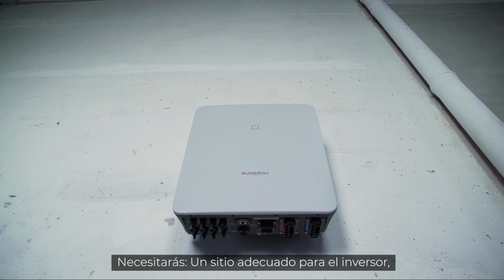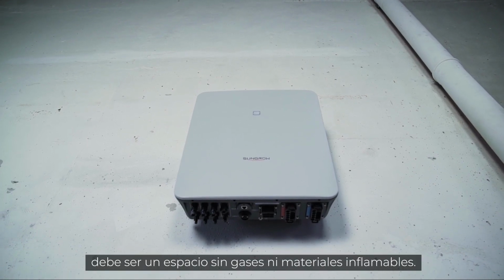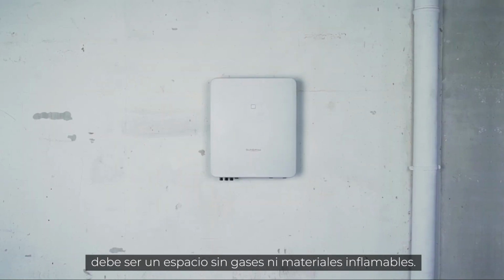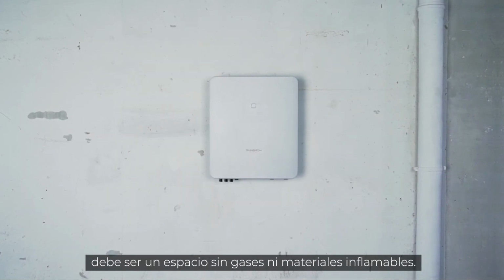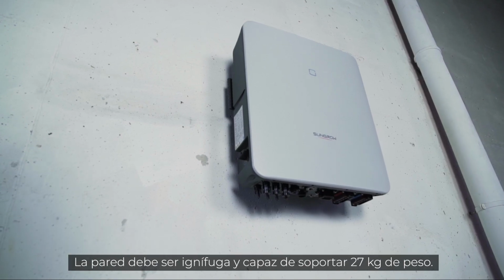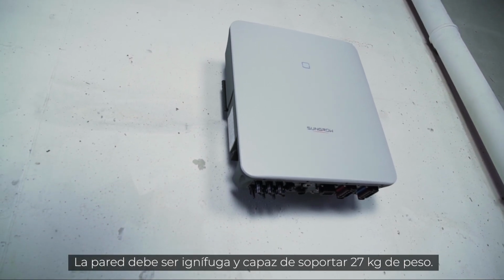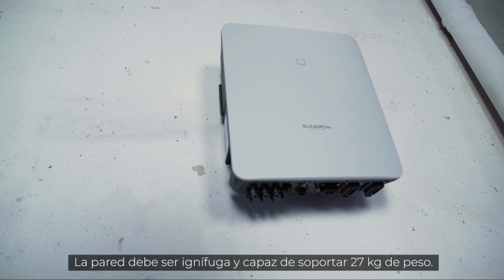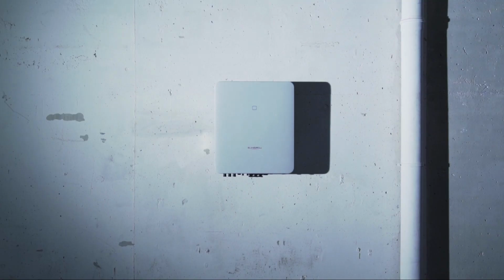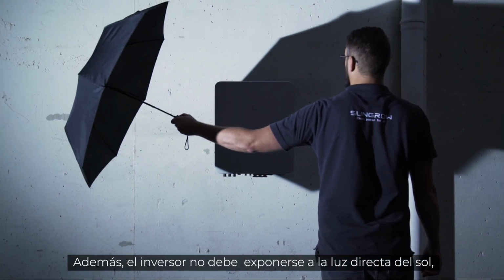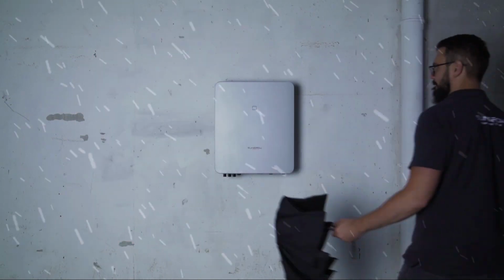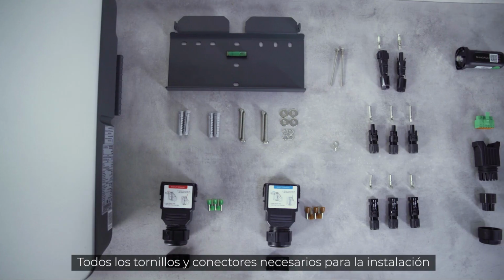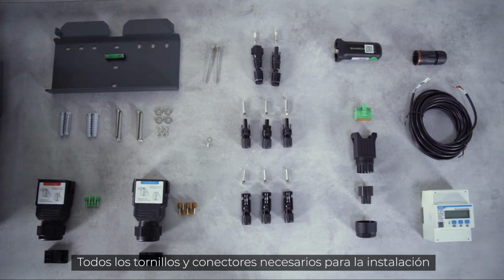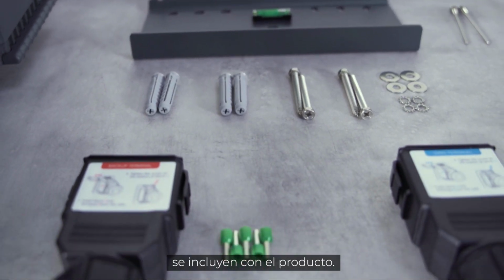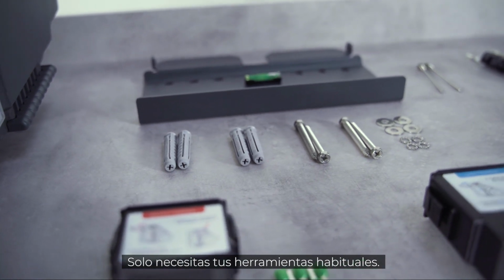You need a suitable place for the inverter. This means it should be a room where no flammable materials or gases are stored. The wall must be fireproof and able to bear the weight of 27 kilograms. Furthermore, the inverter should not be exposed to direct sunlight, rain or snow. All screws and plugs required for the installation are already included in the delivery. You only need your own tools.